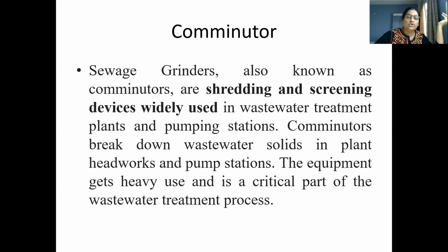One more sentence I told you: comminutor and screening will be provided in parallel, not in series. Why do we need to provide them in parallel? A comminutor is a mechanical operation, so there is a chance of its breakdown.